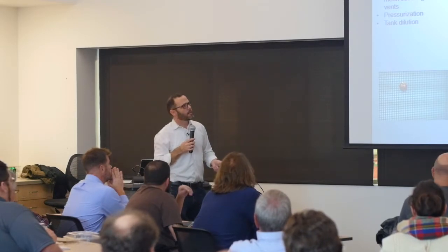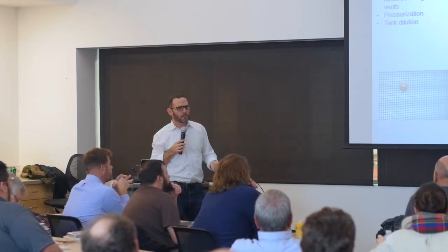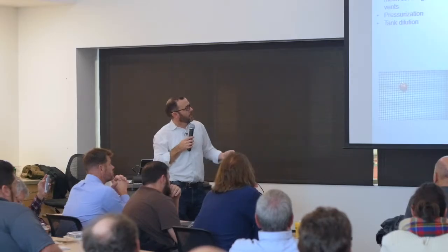What was your relative humidity target? It was about 75%, and it's basically 75 degrees to 80 degrees. I mean, it's a tall space, so there's a lot of temperature stratification. At the top, it's more like 80, 85, and can even be hotter on sunny days. There's a lot of lighting up there. Down at the bottom, it's more like 75, so a little more comfortable at the bottom. As you wind your way up the ramps, it gets much warmer. But the plants like it.